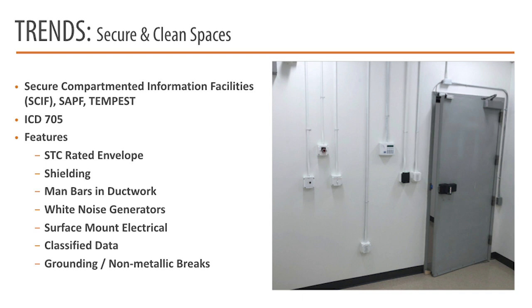You generally have multiple layers of drywall, often with a layer of RF shielding between the layers. Any ductwork passing through the space is 96 square inches or larger, with man bars, an inspection port, and white noise generators in ductwork and chases. You've got surface mount electrical, since you don't want to compromise the integrity of the secure envelope you're creating. In addition to general data coming into the room, you often have a local server, cable tray under the ceiling, and you're running a classified local network as well. Any piping coming in and out of the space is either grounded or has a section of non-metallic piping built in.